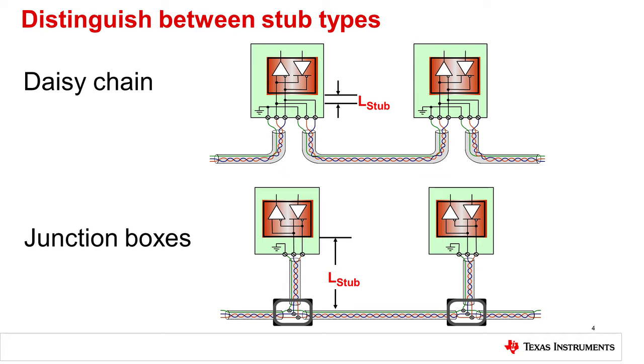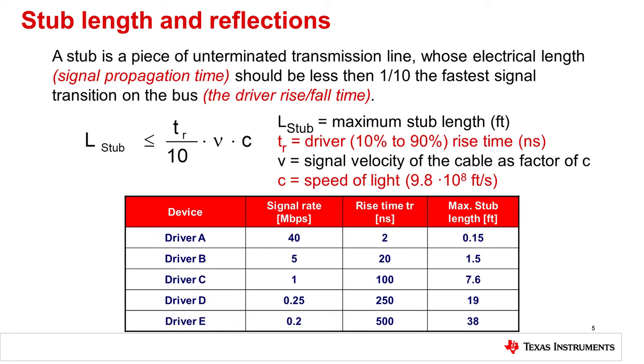The junction box approach can also work well, but ideally the stub length should be minimized to reduce reflection. In cases where the stub length cannot be reduced to a reasonable length, the data rate may need to be slowed down in order to reliably communicate. This is a general rule of thumb, not a firm rule. The maximum acceptable stub length can be calculated using the equation provided.